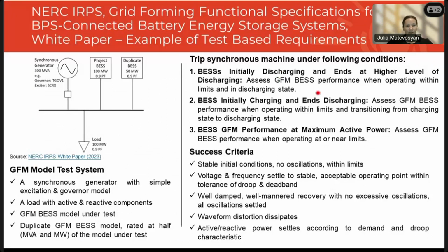So I wanted to bring up the test of loss of last synchronous machine. I see some confusion sometimes when we're talking about these tests, and people think, oh, you need to dimension a grid forming battery to support part of my grid, and it may be a large part, maybe it requires a lot of over dimensioning. That's not what it is about. It's just to test basically the capability of a battery to be grid forming and operate without any synchronous machine and survive disconnection of the last synchronous machine. So this is a test that is applied to a model, a grid forming inverter model.